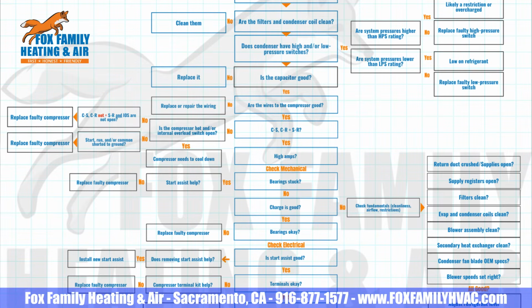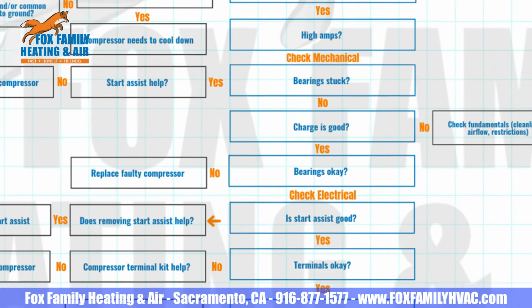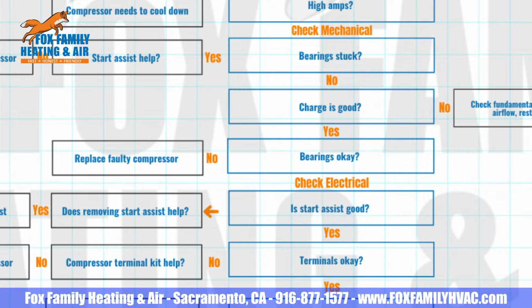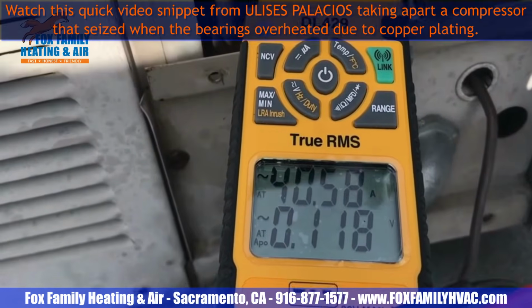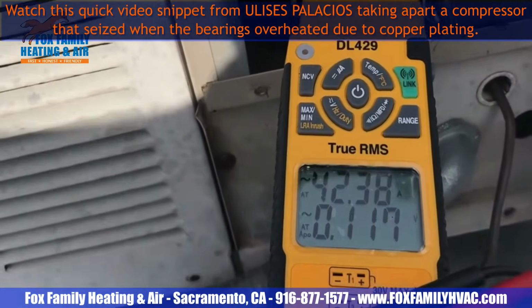Is the problem mechanical? The bearings inside of the compressor that move the scroll could be worn. Worse, they could be stuck. You're going to be able to tell if it's struggling by reading a higher amp draw than the data plate suggests.